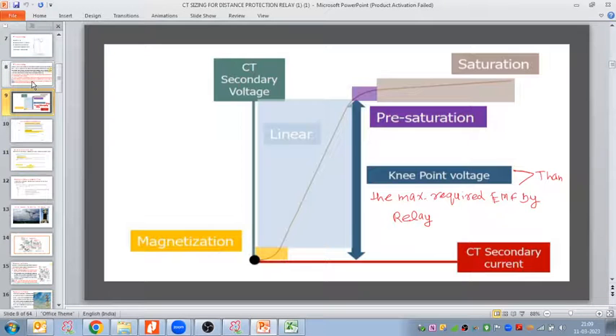So the CT knee point voltage, this is all we have seen. Then here we have seen this saturation curve for the CT. This voltage we call the knee point voltage. Thereafter, the CT core enters into saturation, because the CT core is designed with CRGO material, and no magnetic core is designed for infinite saturation. So the core will have some saturation. But my requirement is that the CT core should not saturate in the event of a fault before the relay operates. Or we can say that the knee point voltage in the CT should be more than the required voltage by the relay. So the knee point voltage should be greater than the maximum required EMF by the relay. So what we are doing is calculating the maximum required EMF by the different relays.